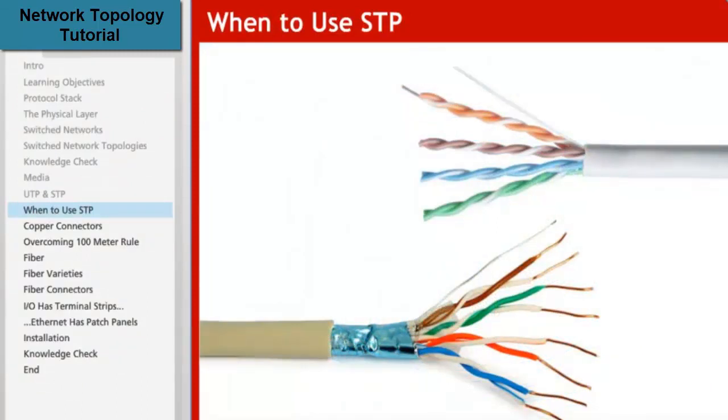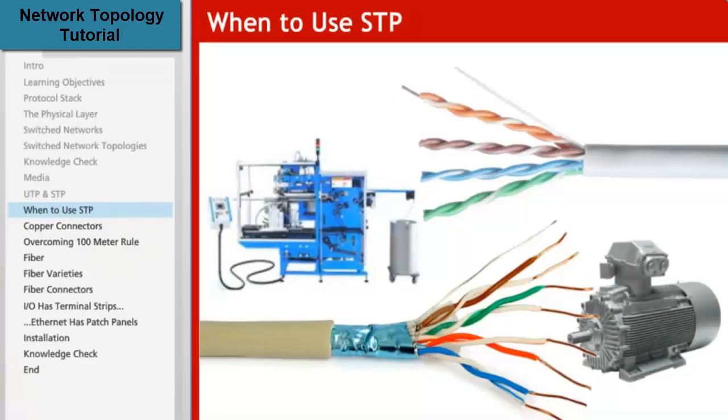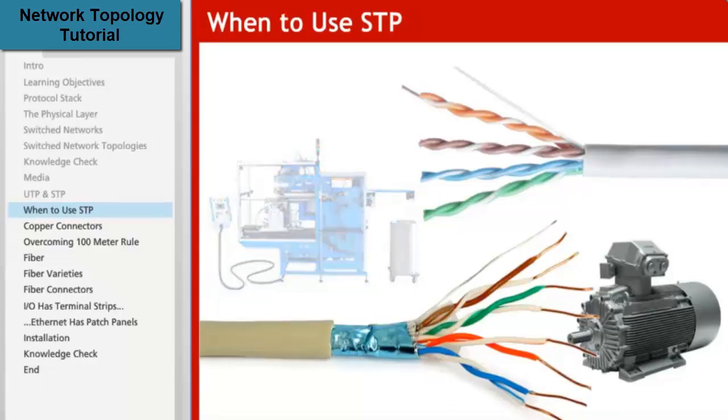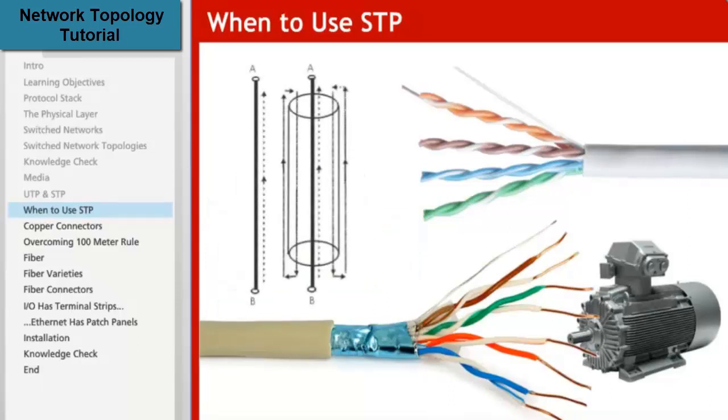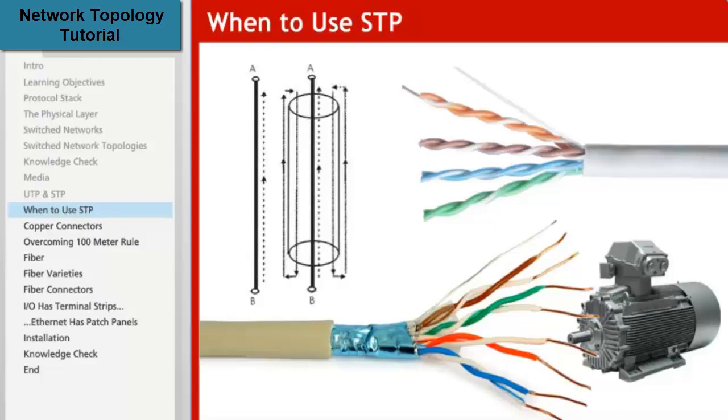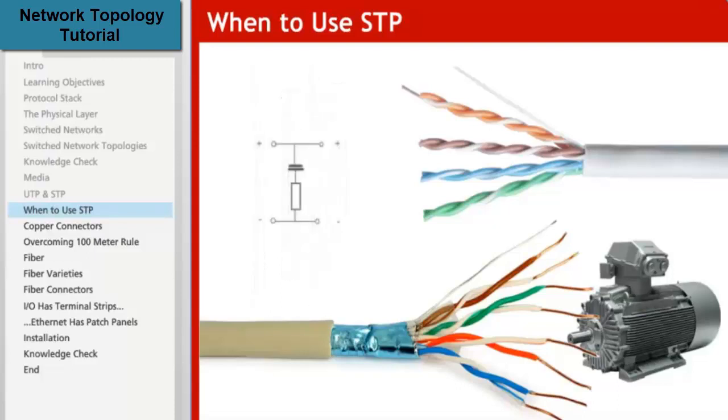Shields help to reduce noise coupled to the balanced cables by acting as a barrier around the conductors. In the presence of strong electrical currents, shielding can be very important. However, shields can introduce their own problems as they may end up carrying ground currents due to ground offsets within the building's grounding system. At worst, these currents can cause equipment damage. At best, they can be disruptive to the network communications. A properly designed system reduces the chance of ground loops by isolating the shield at one end of the channel from ground. Properly designed end devices provide this isolation through the use of an RC network. The switch end of a shielded channel is always grounded if the switch is grounded. If properly grounded, shielded cables are useful in reducing communications error rates in the presence of high noise.